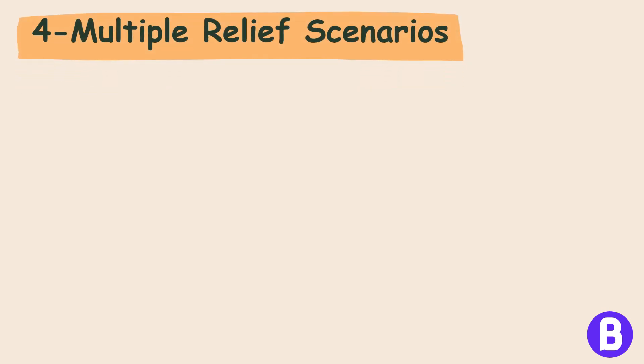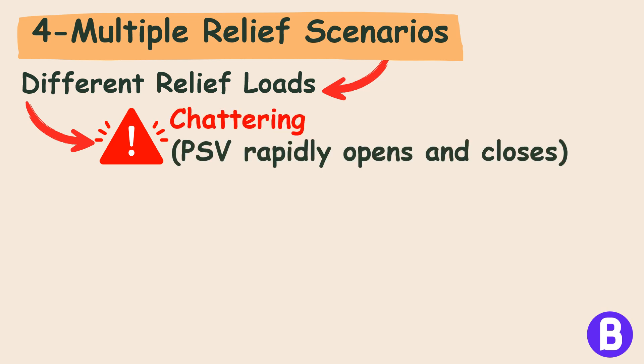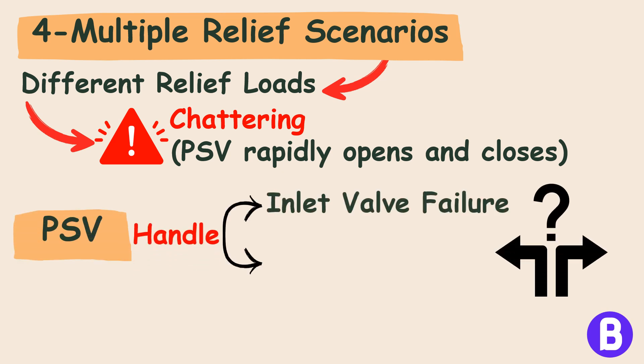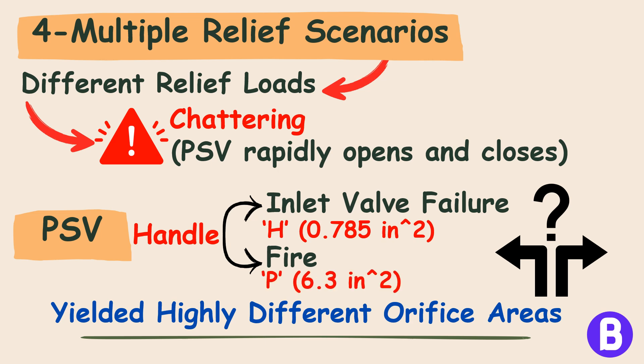Factor 4: Multiple Relief Scenarios. Various relief scenarios can lead to different relief loads on a PSV. If not managed properly, this can result in chattering — a condition where the PSV rapidly opens and closes. Suppose we have a PSV that should handle two scenarios: one for inlet valve failure and the other for fire. When calculating the orifice area for each scenario, they yielded highly different orifice areas. For instance, an inlet valve failure might require an orifice size designated as H (0.785 in²), while an external fire scenario might necessitate a much larger P designation (6.3 in²). This disparity presents a dilemma.